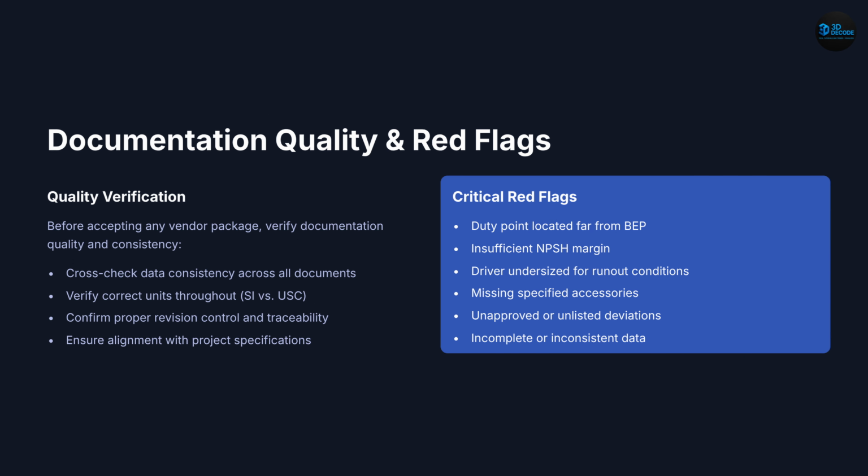Slide 16. Red flags. Watch for duty point far from BEP, low NPSH margin, undersized driver, missing accessories, and inconsistent data. These are major warning signs.